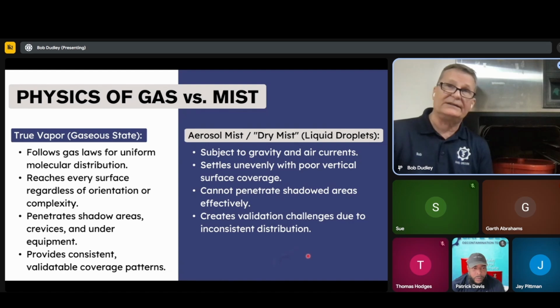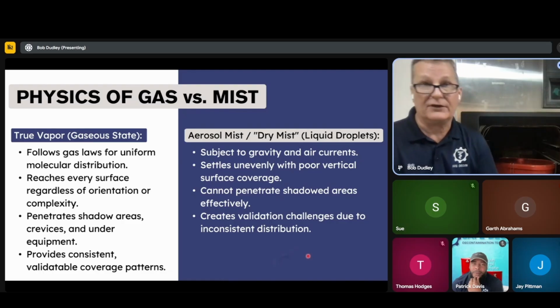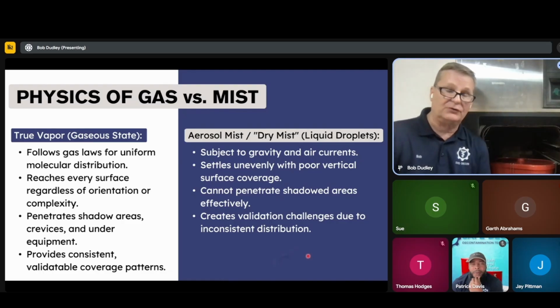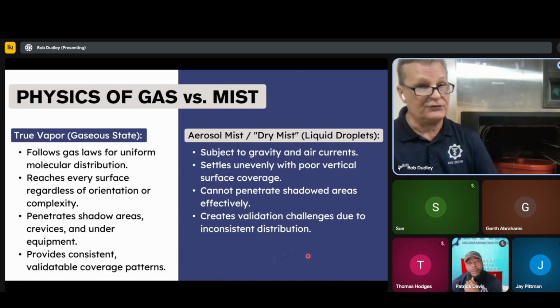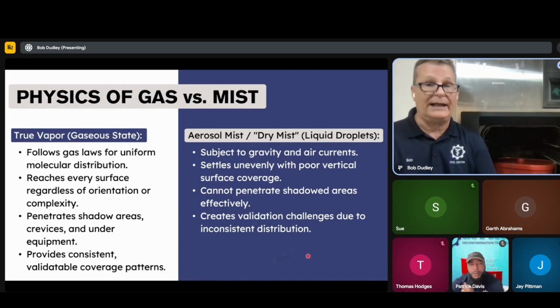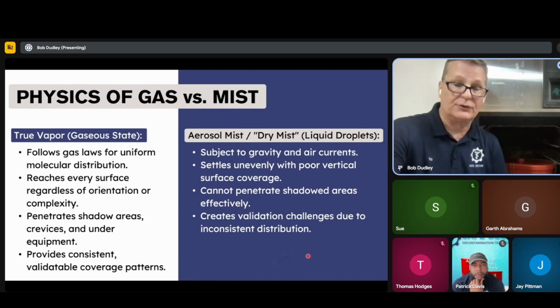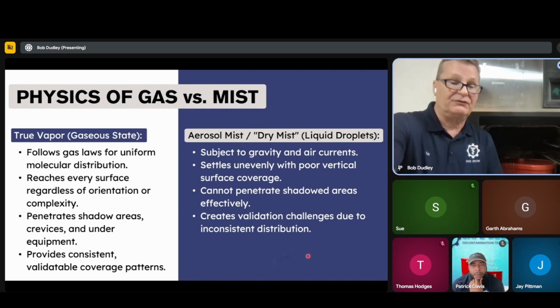A good way to test your autoclave to see whether or not you're running true gas or you're having mist problems or a problem with your autoclave is you can take a paper towel and you can put it in your autoclave, run a cycle. When you open that door and pull that paper towel out, it should be dry. That's if it's running correctly. If it's damp or wet, then you're having an issue with your autoclave. But that's just a fun fact.